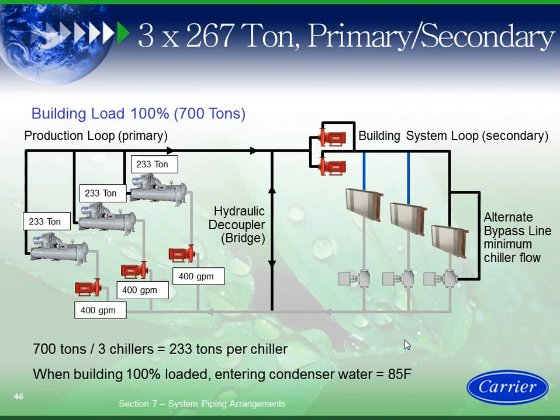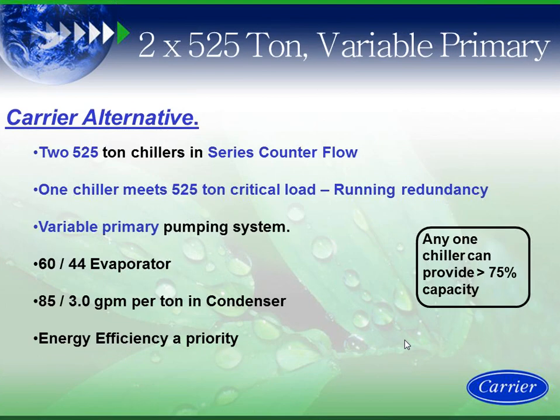So what we did is we said, let's look at an alternative to this. Okay, let's look at 2 525 ton machines. And then what we're going to look at here is something called running redundancy. Okay, so I have 2 525 ton machines, and I'm going to do series counterflow. At any time, if something happens to one machine, we have a 525 ton critical load that's met. And we're able to do that while the machines are running, which means there's less downtime in overcoming that thermal bullet in the system of the chill water system.